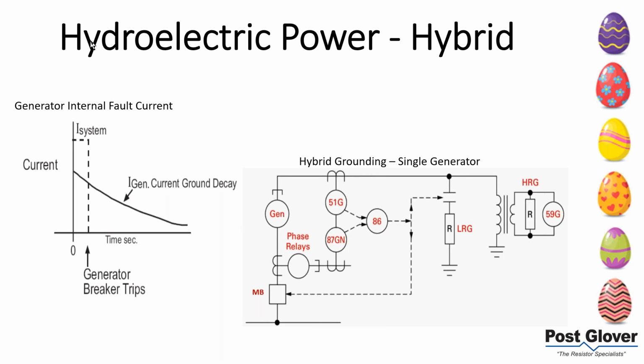Just some more details about generators, medium voltage. I want to touch briefly on hybrid resistance grounding. Essentially, the first illustration here shows a potential internal fault from your generator. When you have an external fault, everything works as you would expect, as I just laid out in the previous slide. But when you have an internal fault, you're going to have to wind down after you trip, and this is what you're going to be getting.